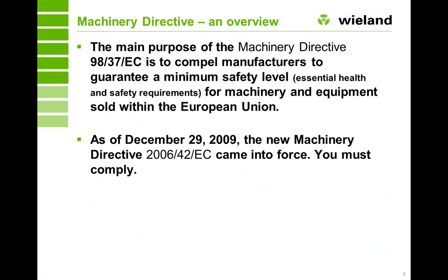The old directive was 98/37/EC, and the new one is 2006/42/EC. This came into force as of December the 29th, 2009. You must have complied with that from that date for any machine that you have supplied, installed, or built since that date. There is no question, there is no period of allowance where you would have been allowed to supply anything that wasn't compliant. You must comply with it from that date.